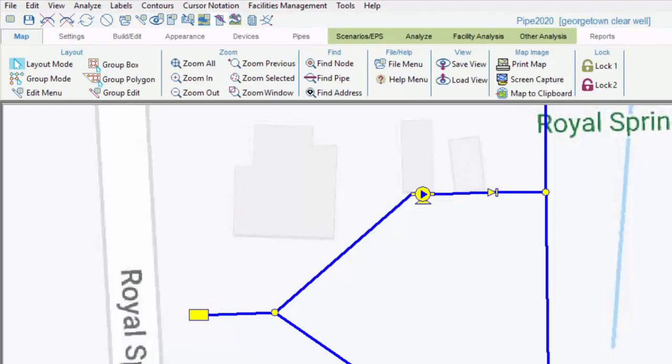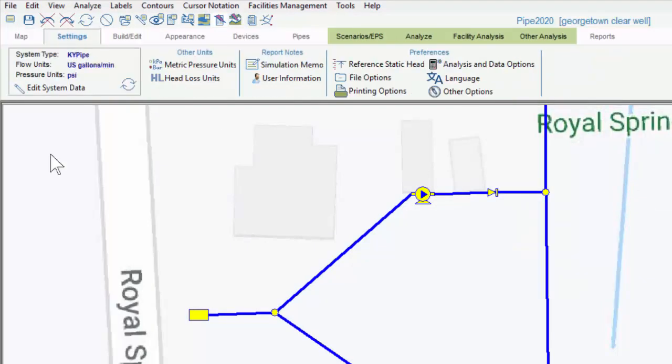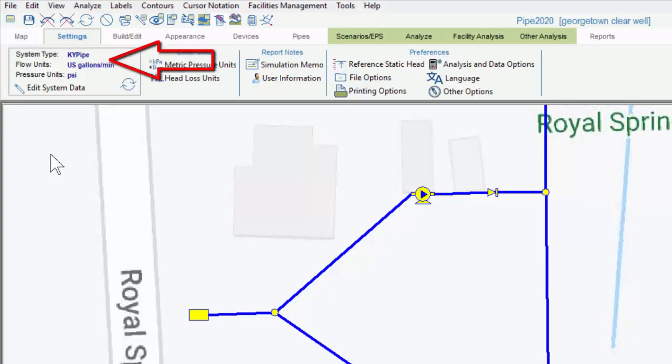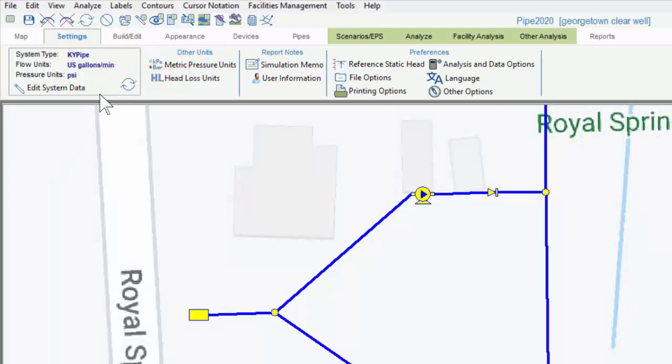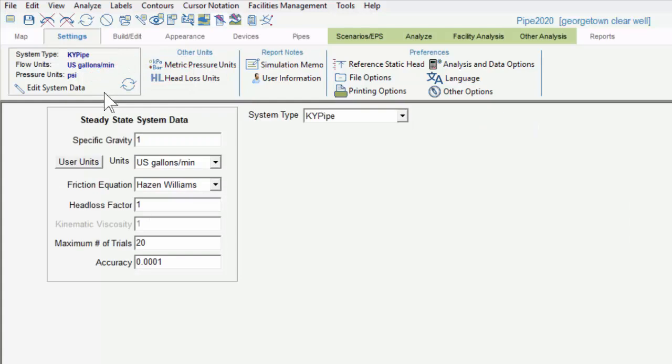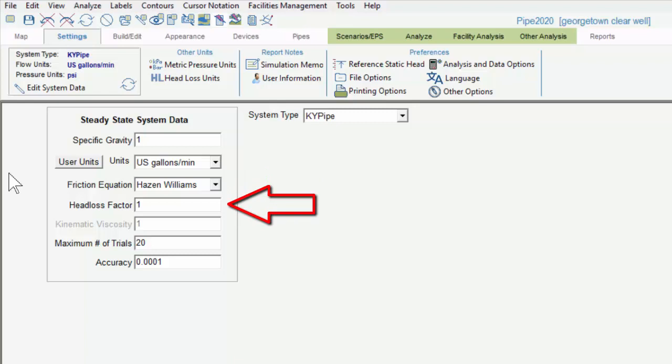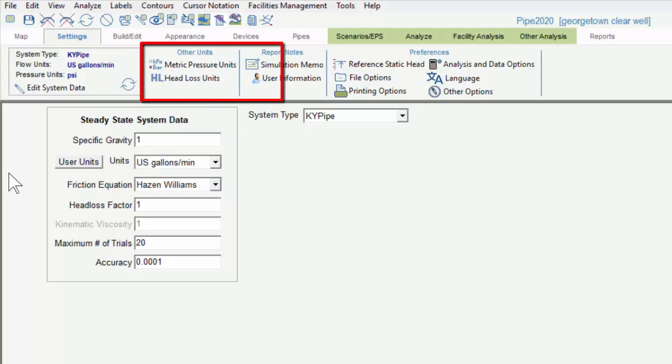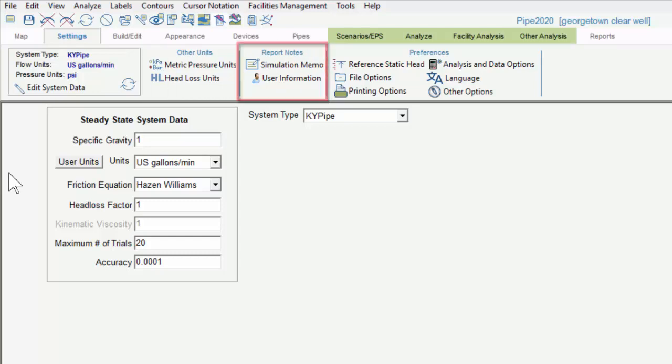The next tab is the Settings tab, which contains global parameters that apply independent of the contents of the map area. The System Data menu has a thumbnail display here, which shows which analysis engine you are using, as well as global flow and pressure units. If we click on the thumbnail, we can see additional information, including the friction equation, the head loss factor, kinematic viscosity if we're using a liquid other than water, and the analysis variables used to determine if the program can achieve mathematical convergence. We also have additional unit information and simulation notes in the submenus.